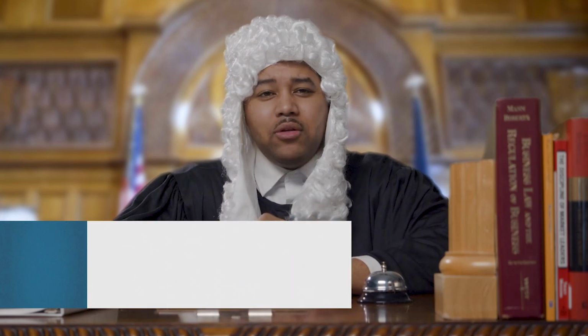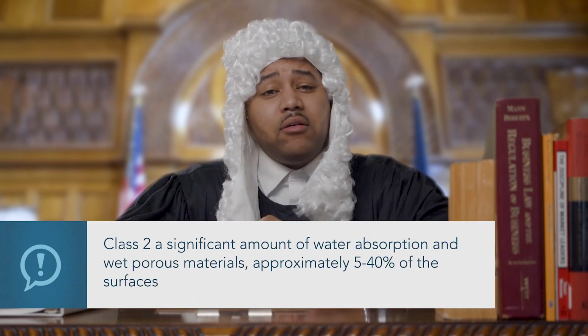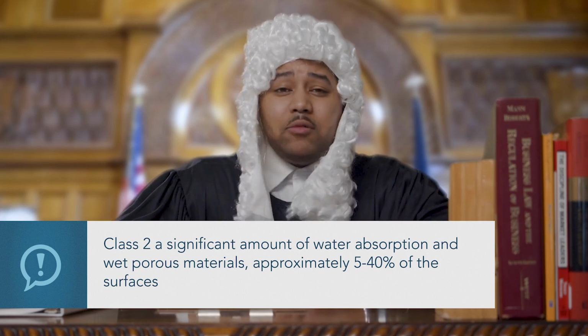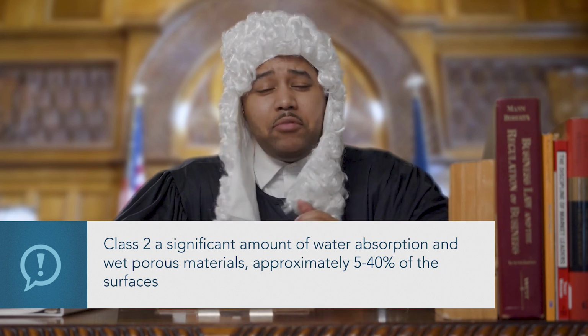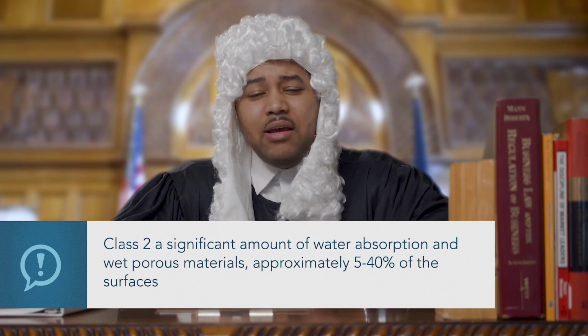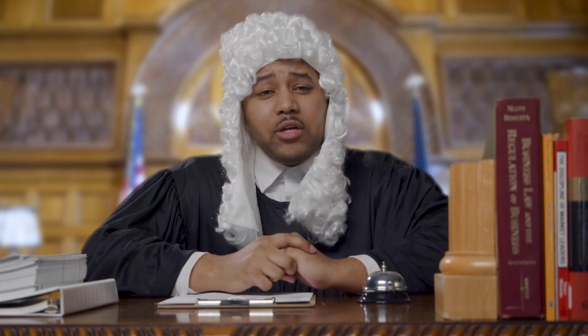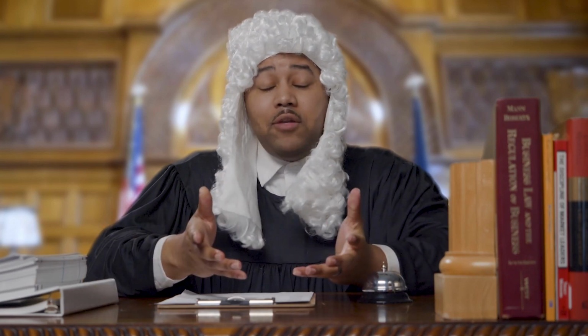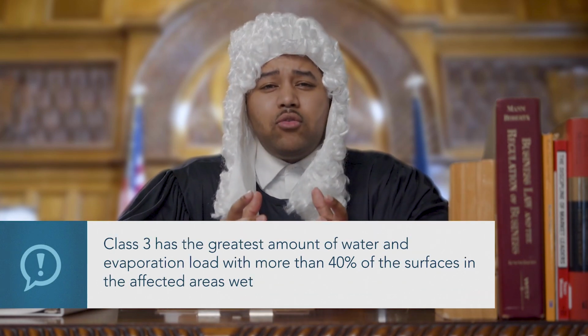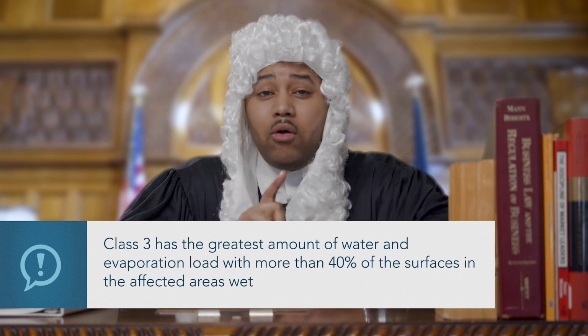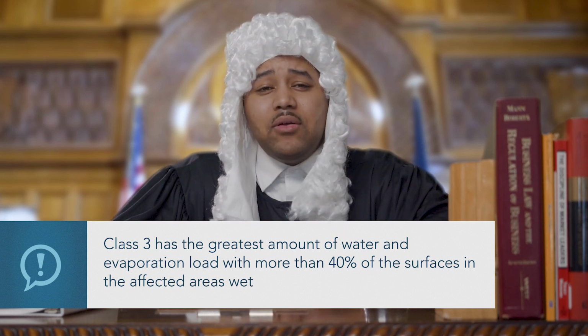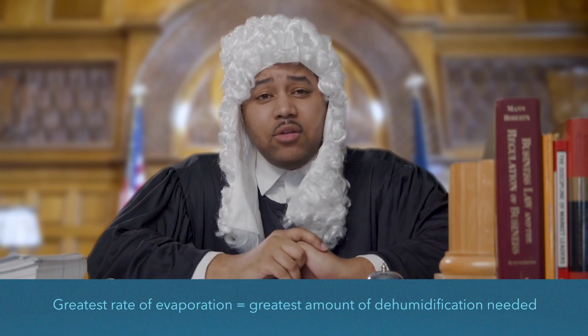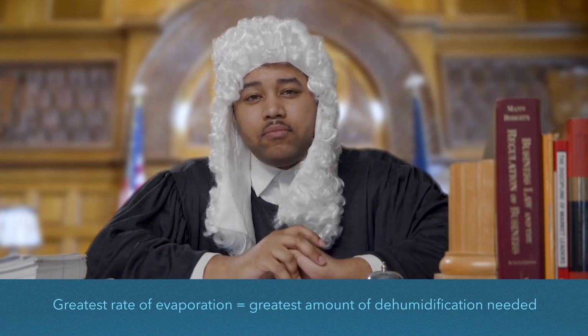Now, Class 2 is a significant, and some would say large, amount of water absorption and wet porous materials. Approximately between 5 and 40% of the surfaces in the affected areas are wet. So naturally, this means that a greater amount of evaporation will occur, and naturally more dehumidification will be necessary. But the Class 3, it says the greatest amount of water and evaporation load with more than 40% of the surfaces in the affected areas wet. As expected, it would also have the greatest rate of evaporation and need more dehumidification.